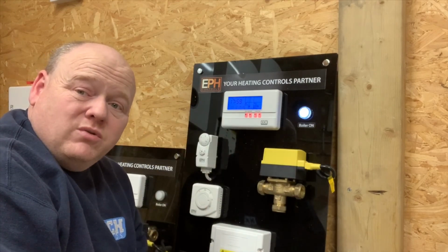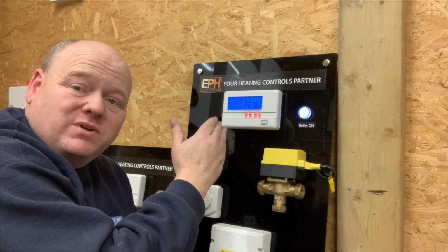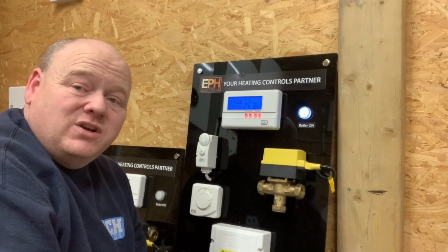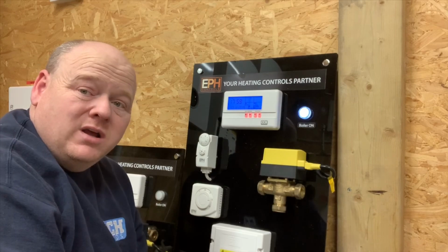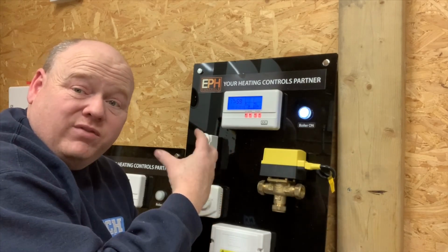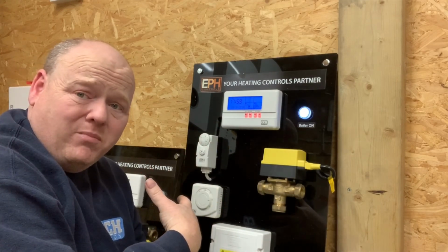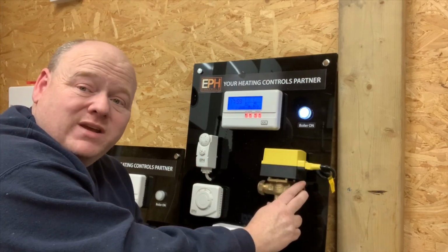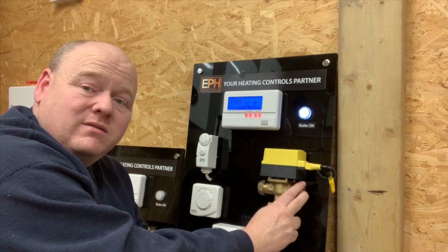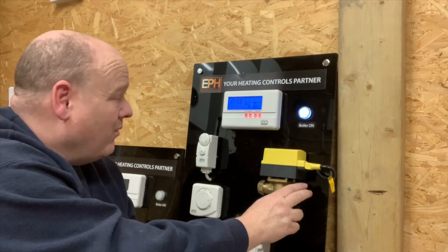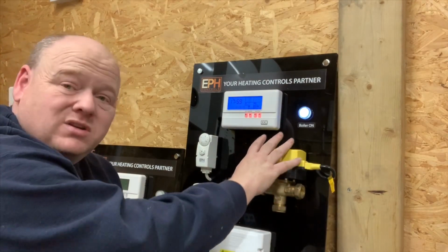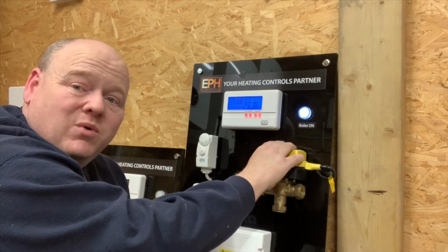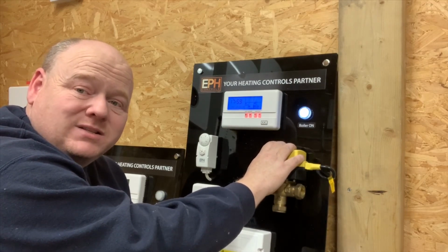Or if they don't want to do that, then set the times to a different time to the heating, especially in the morning. And then when you turn your heating on in the morning, the flow from the system, whether it be from the pump from the boiler or the pump in the airing cupboard, all the heat can go around the heating system, and the heating would get warmer a little bit quicker that way. So that's the overview of the Y plan system. So now what we'll do, we'll have a look at the S plan heating system.